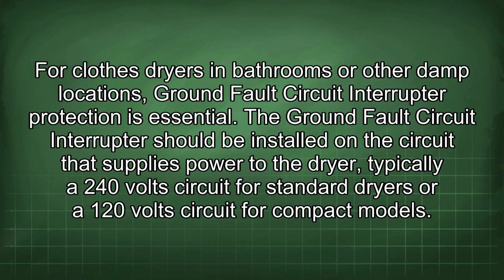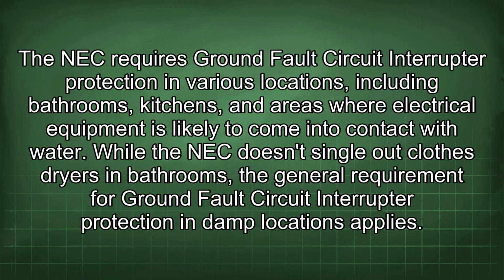For clothes dryers in bathrooms or other damp locations, ground fault circuit interrupter protection is essential. The ground fault circuit interrupter should be installed on the circuit that supplies power to the dryer, typically a 240-volt circuit for standard dryers or a 120-volt circuit for compact models. The NEC requires ground fault circuit interrupter protection in various locations, including bathrooms, kitchens, and areas where electrical equipment is likely to come into contact with water. While the NEC doesn't single out clothes dryers in bathrooms, the general requirement for ground fault circuit interrupter protection in damp locations applies.